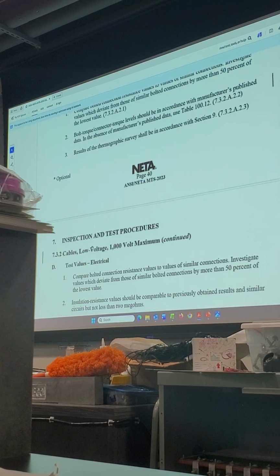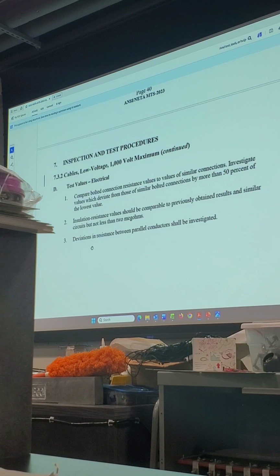We're going to see that time and time again. For low voltage, table 100.12 is even beyond the scope, but it says insulation resistance value should be comparable to previously obtained results, that's our data trend, and similar circuits, but not less than 2 megohms. If you recall 100.12, there was no column showing 2 megohms.